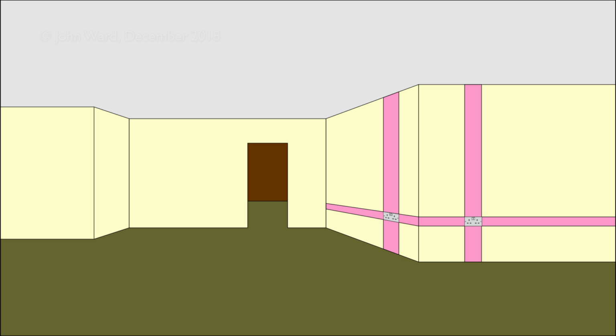Now it's worthwhile considering the future use of the room, because although people are supposed to know where these zones are, it's not always the case that they necessarily follow them or give much care about the actual installation. So for example, if this was going to be a kitchen, it would be a good idea to put the actual cables horizontally between the various sockets that were going to be, say, above your worktop, because if you put them vertically, there's a very good chance that whoever installs the cabinets, whether those be on the ground or ones that are on the wall, they're going to drill holes in the wall to secure those, and of course they could end up drilling right through the cables, and of course they're going to say, well, that was your fault. But put them horizontally between them, that avoids all of that bother in the end. But again, if it's just going to be a normal room like this, generally just pick whatever the shortest route is or the most convenient one.